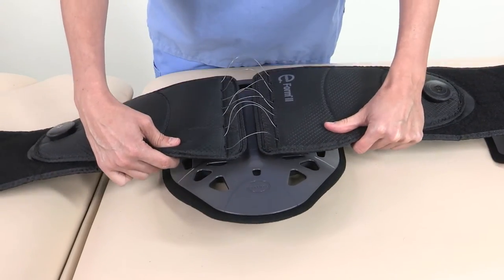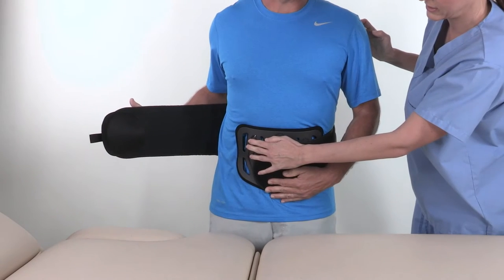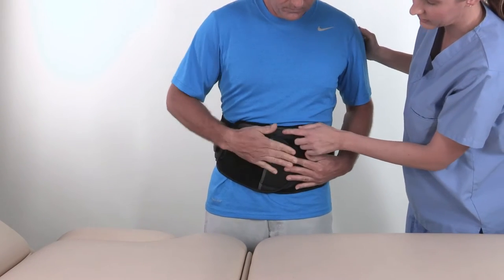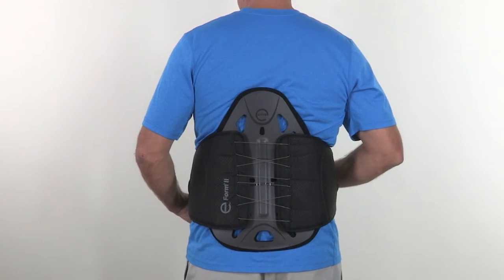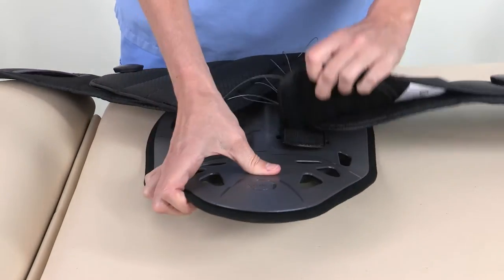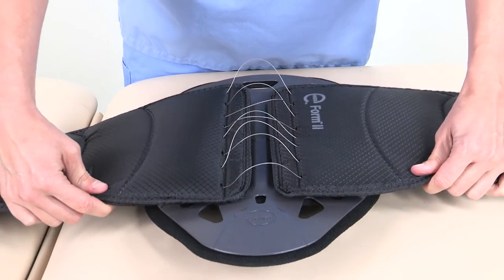Remove the brace and apply the tall rear panel. Have the patient insert his or her hand into the donning mitt pocket. Wrap the front panel belt wing section over the rigid front panel. Note: the glide track should be positioned in the middle of the waist groove. Panel may be adjusted by detaching and resecuring the hook sections vertically on the rear panel section as desired.